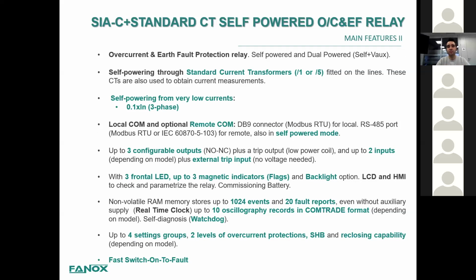Regarding information storage, this relay has up to 1024 events and 20 fault reports. And depending on the model, we can also have 10 oscillography records in COMTRADE format, which is a very useful indication and helps a lot to study and check what faults and reasons for faults have occurred in a particular situation. There is something important on this relay: we also have 4 setting groups, 2 levels of overcurrent protection, second harmonic blocking and reclosing capability.